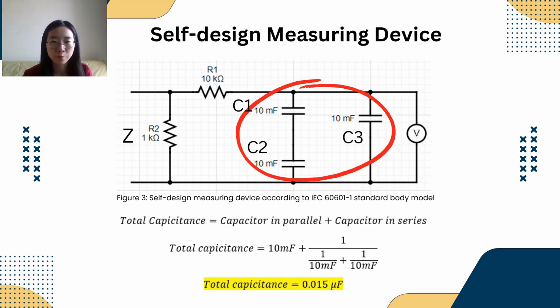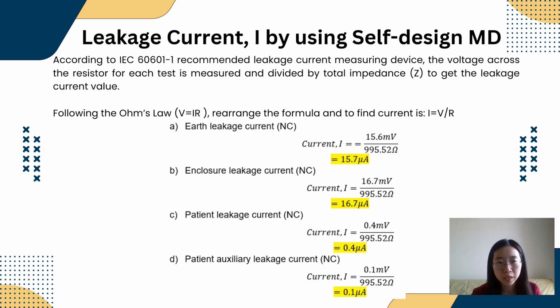For the self-designed measuring device, we use C1 and C2, which are 10 millifarad built in series, and C3 is 10 millifarad that is parallel with C1 and C2. So we can calculate that the total capacitance is equal to 0.015 microfarad. So moving on to the next part, how do we calculate leakage current I by using the self-designed measuring device? According to this IEC recommended LCA measuring device, the voltage across the resistor for each test is measured and divided by the total impedance Z to get the leakage current value. So we can get earth LC equal to 15.7 microampere, enclosure LC equal to 16.7 microampere, patient LC equal to 0.4 microampere, and patient auxiliary LC equal to 0.1 microampere. All of this is in normal condition.